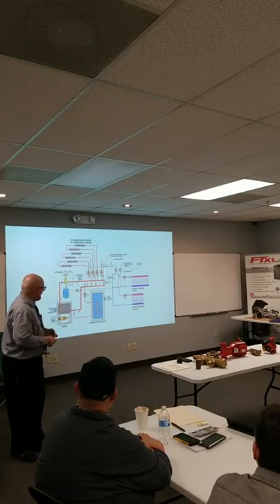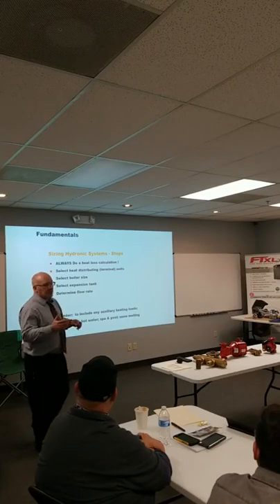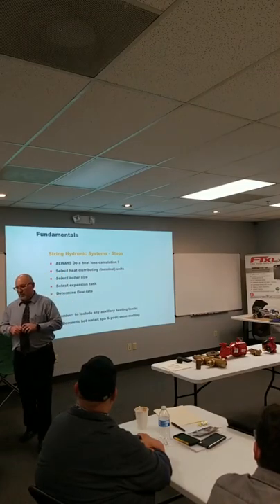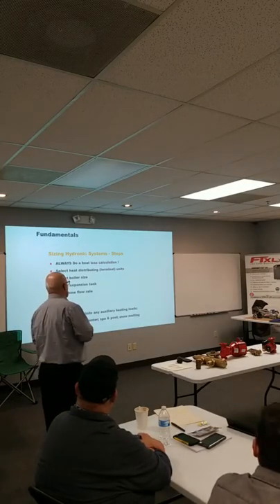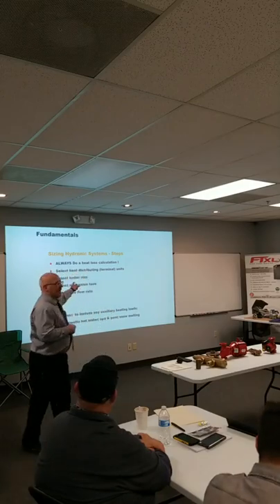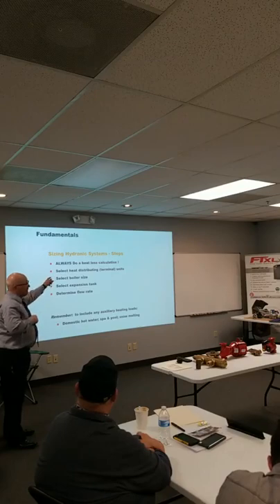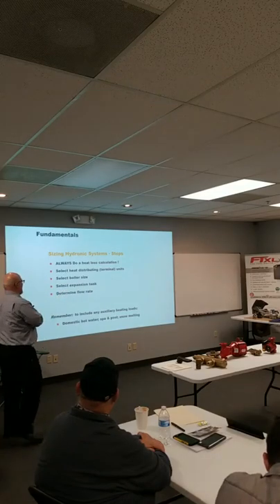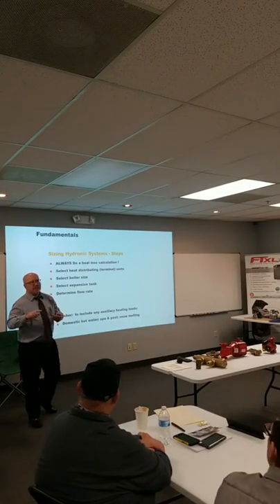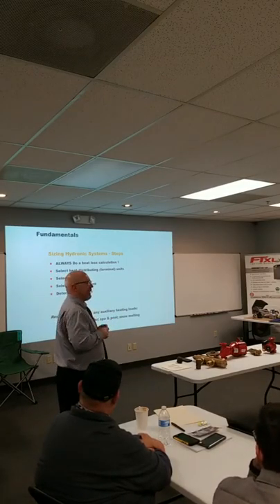There's a lot of different things we can do with water that we may not be able to do with heat. So I'm going to get on my soapbox here: I also sell boilers. And when we replace boilers, I don't care residentially, commercially, whatever it is, how do we replace boilers? Because the boiler size, the BTUs, remember Fahrenheit over there? The BTUs we have to provide to that system determines everything else in the system. It determines the amount of radiation, pipe size, pump size. It determines everything.